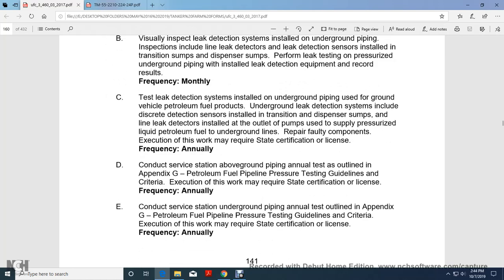Test the leak detection system installed with the underground piping system used with ground vehicle petroleum fuel products. Underground leak detection systems include discrete detection sensors installed in the transition and dispenser sumps, and line leak detectors installed at the outlet of pumps used to supply pressurized liquid petroleum fuel to the underground lines. Repair faulty components by excavation. Execution of the work may require state certification and license, annually.